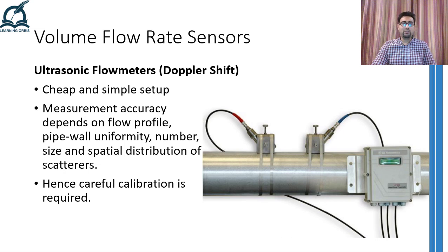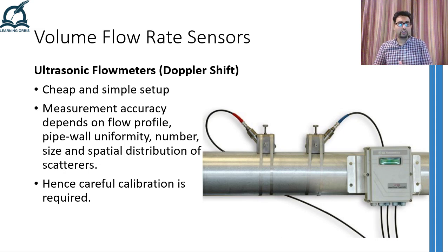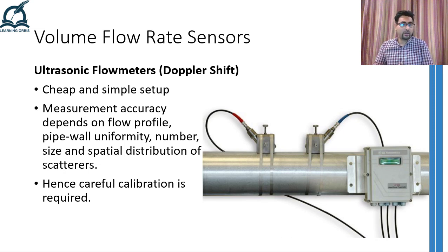Multiplying the speed of the fluid with the cross-sectional area of the pipe gives us the volume flow rate. The strength of the reflections received by the ultrasonic detector is dependent on a number of factors, for example the flow profile, uniformity and internal structure of the pipe, the number, size and spatial distribution of the particles present in the fluid creating the reflections, and many other things. Hence, careful calibration is required when using these kinds of flow meters.